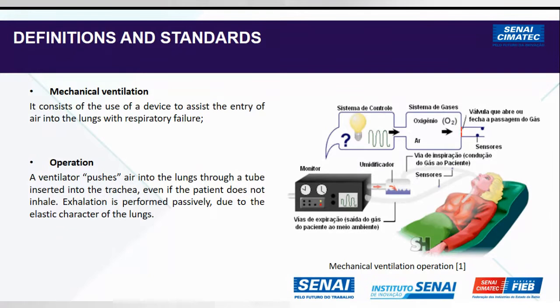You see in the picture, it's a control system. This control system presets the parameters of ventilation. You control the insufflated flow, the inspiration volume and the inspiration pressure. You control the gas system to mix the oxygen and the medicinal air in different concentrations to push the air into the patient, and you preset the respiratory frequency. It uses many sensors to control and check the preset parameters for ventilation that are defined by the medical team.